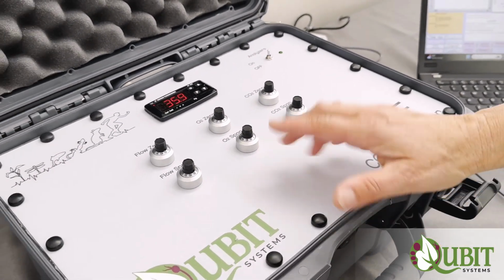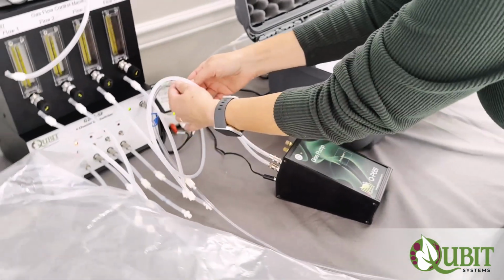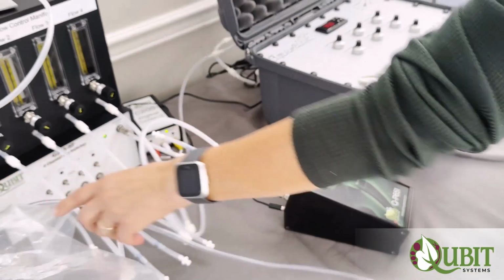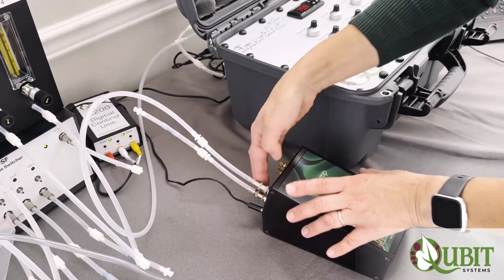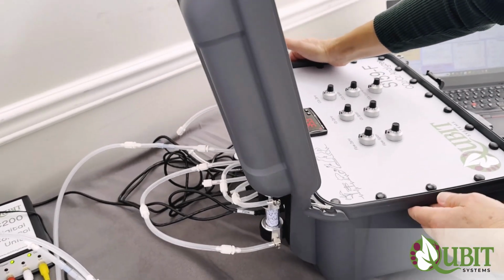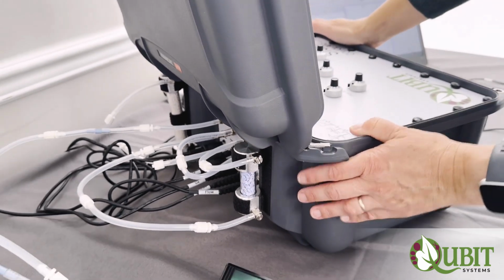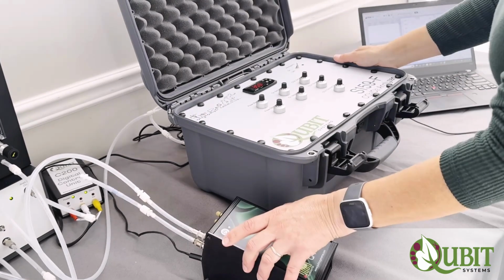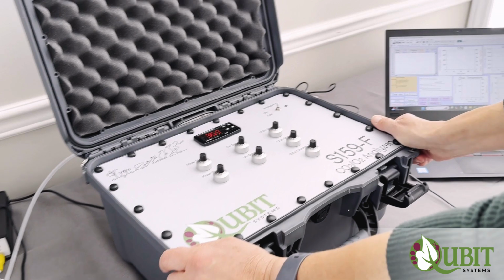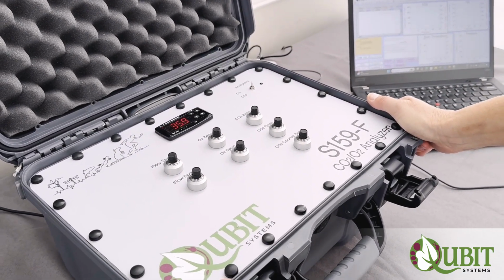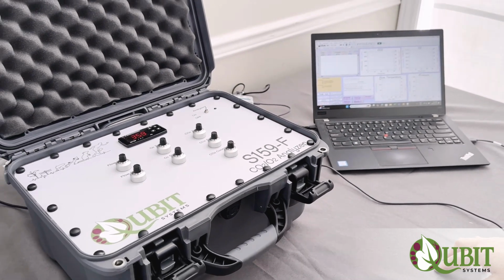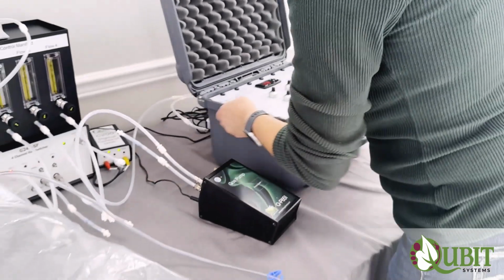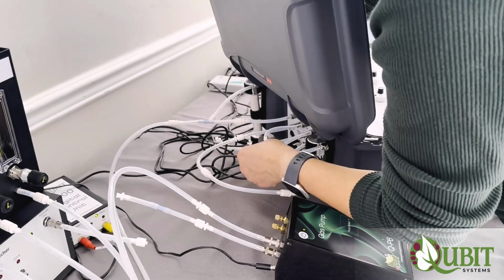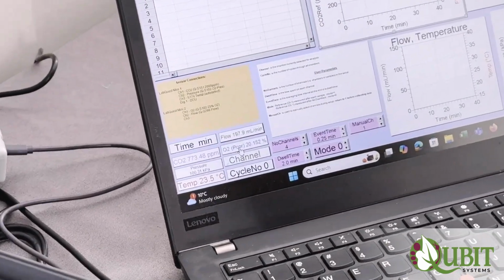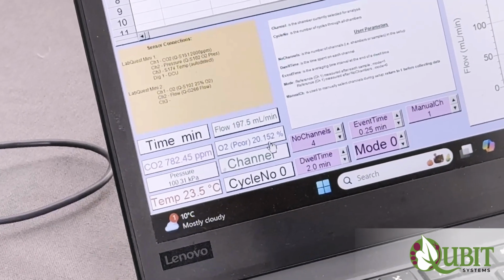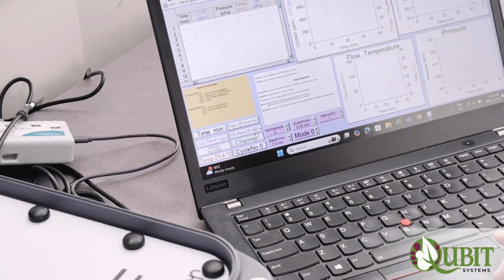Okay, and now for the second point of the oxygen sensor, we will disconnect this bag with the standard CO2 and pure nitrogen, and we're just now bringing in room air through the pump to the analyzer. But remember, this room air is going through a drying column, and dry outside air contains 20.95% oxygen. So to calibrate the oxygen sensor, one can use just outside air that has been dried. So we're gonna wait for that gas to go through the sensor and the analyzer. So we now have dry air running through the oxygen sensor. You can see the reading is stabilized around 20.15. And as I mentioned, dry air is going to have 20.95%.